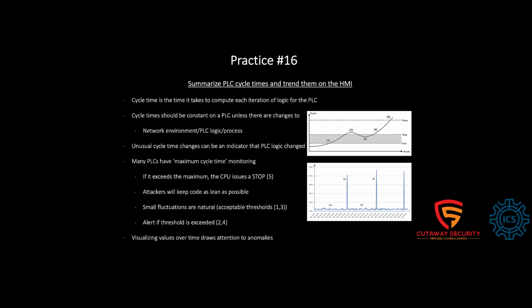So most of these were diagnostic tools capable of doing this work, but were never really done because, who needs that? Like, why would you worry about CPU usage if everything is fine and the PLC is running? There was never any concern about attackers manipulating the CPU or the PLC code and that causing these spikes to happen. But that wasn't something the operator or the controls engineer was required to track. So absolutely, this is something that you additionally configure.